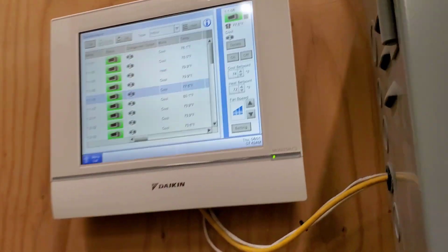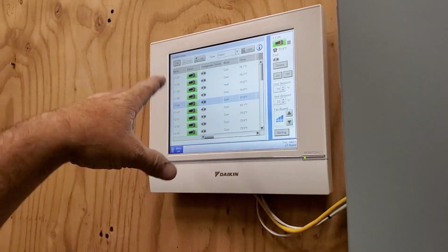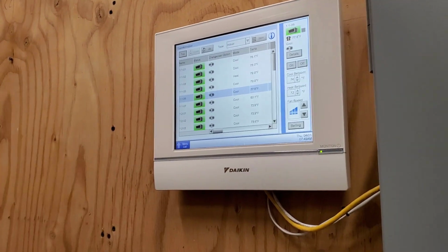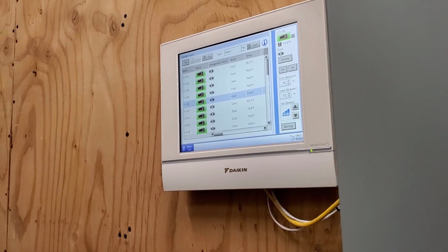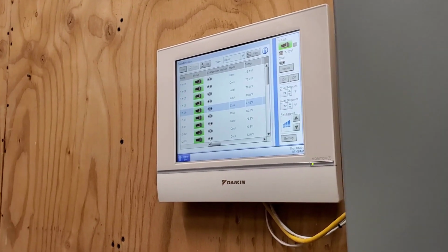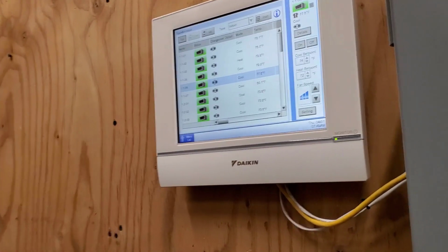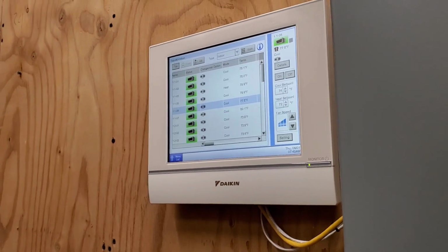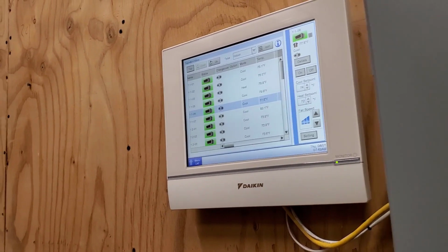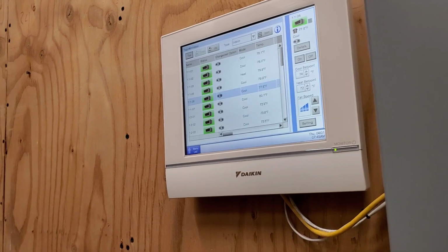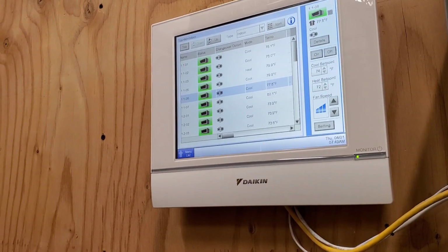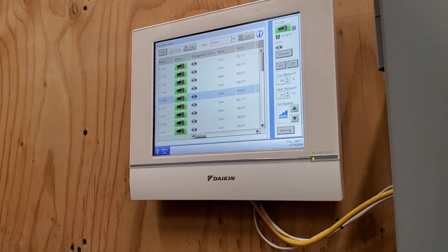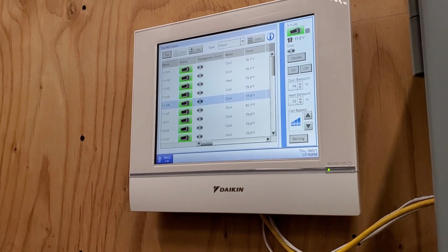I've had that happen to like three or four random fan coils on this Daikin system at the site. First time I actually tore into it, checking resistances of the motors and everything, and then before I even put the new fuse in there, just checking everything, hit all that work, and then it just worked fine. And then I've had it happen to random ones after that, and then on other job sites that they also installed these Daikin systems in, the VRV systems. I believe it's just inrush current charging the capacitors.